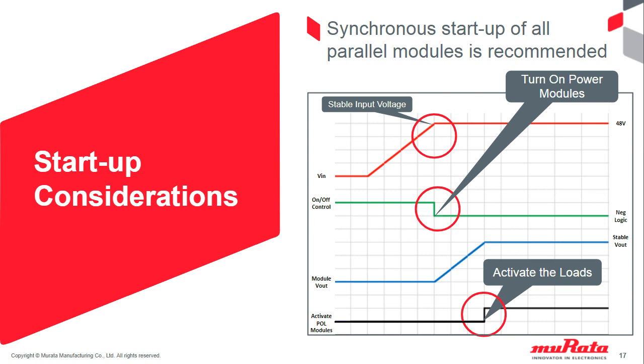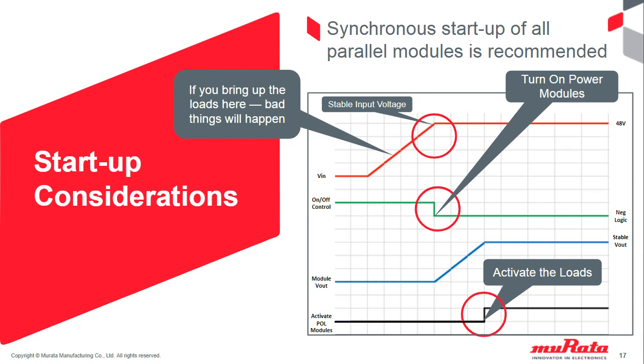Now, what you don't want to do is activate the load during the ramp up of the power module. Bad things can happen. Speaking of just one particular instance, the module could go into a current limit mode and oscillate back and forth, which could disturb your loads. In other words, bad things can happen. You want to have a controlled startup at all times.